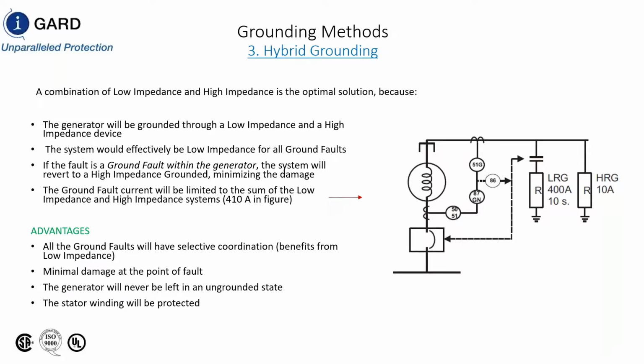How did you size the neutral wire? That's a good question. There is a formula in NEC, because the cable doesn't need to be sized to carry 400 amps continuously. If it's a continuously rated resistor, then yes, you have to have a continuously rated wire. If it's a 10-second resistor, there is a formula in NEC and in IEEE 3003.1 which allows you to decrease the size of that wire, but you have to ensure that the current flowing through that wire does not extend beyond the temperature rating of that wire.